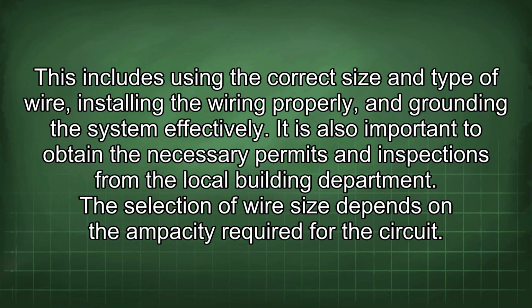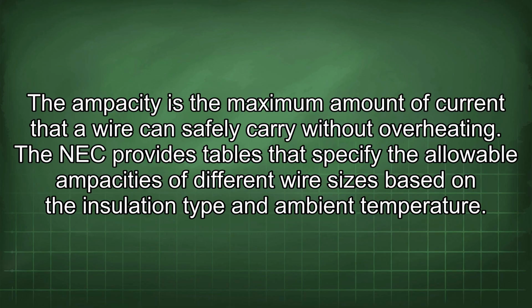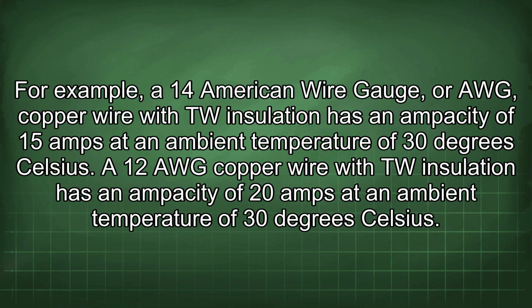The selection of wire size depends on the ampacity required for the circuit. The ampacity is the maximum amount of current that a wire can safely carry without overheating. The NEC provides tables that specify the allowable ampacities of different wire sizes based on the insulation type and ambient temperature. For example, a 14 American wire gauge, or AWG, copper wire with TW insulation has an ampacity of 15 amps at an ambient temperature of 30 degrees Celsius.